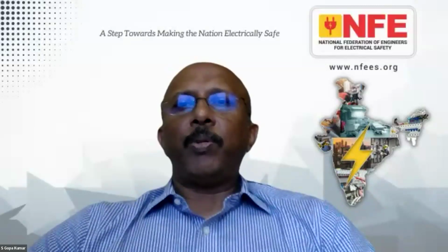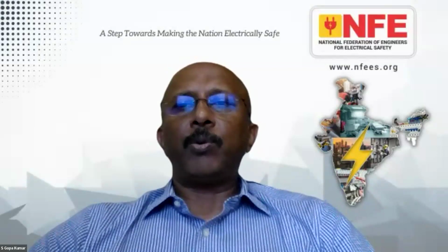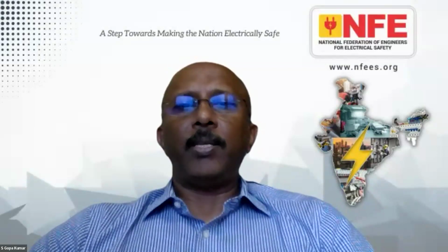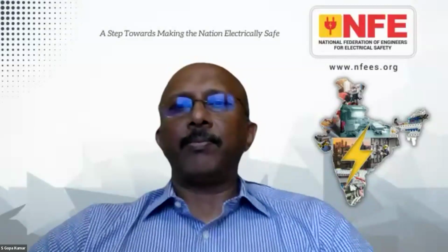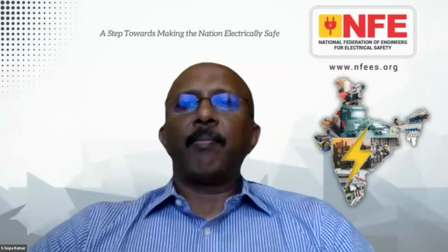So we also have one more person who has raised the hand, Mr. Shovan Babu. Mr. Shovan Babu, if you have any question, please ask. Yeah, I think he has put a question: how to calibrate a loop impedance tester? We have a unit of another make. Is calibration necessary like any other measuring device? Sir, as per ISO guidelines, yes, any measuring device needs to be calibrated once a year. It may be from any company, but it has to be calibrated from a proper calibration lab to ensure that the particular measuring device is working fine.